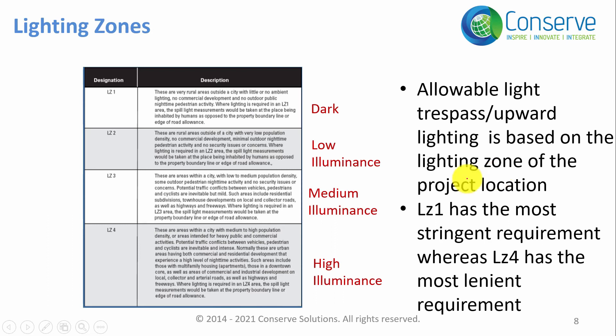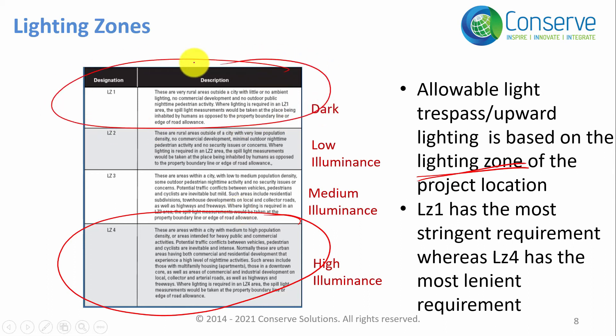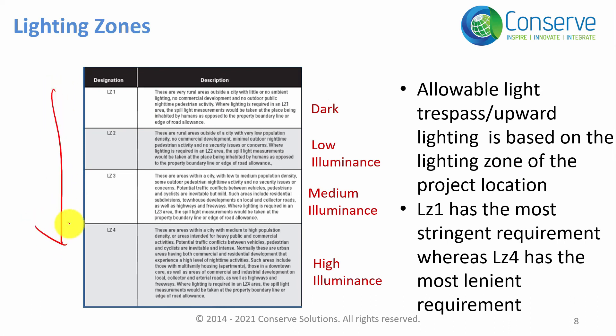The allowable light trespass limit depends on the lighting zone of the project location. If the project is in a commercial area in the city, it falls under Lighting Zone 4 (LZ4). If the project is in a forest area, it falls under Lighting Zone 1 (LZ1). The higher the lighting zone number, the more light trespass is permitted. LZ1 has the most stringent limit, while LZ4 has the highest allowable limit.